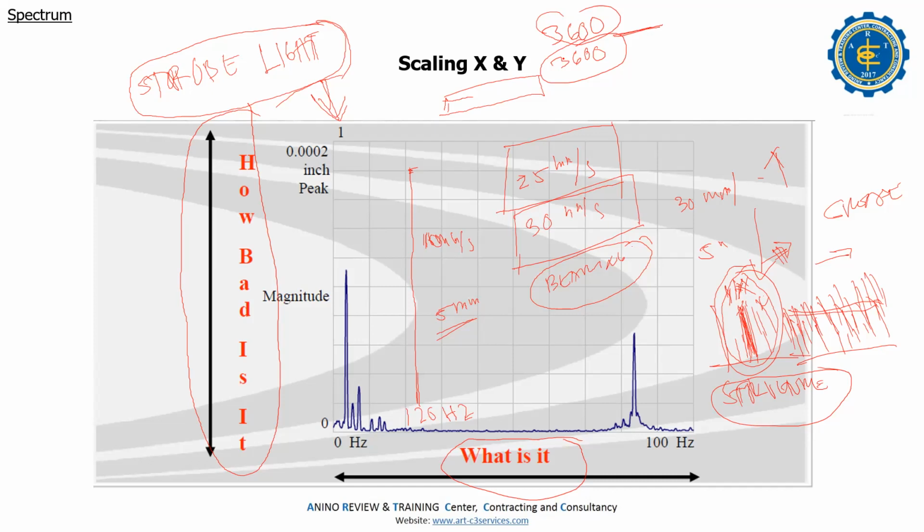Yeah, because when I do analysis, sometimes the 3x peak will come bigger. So I used to think 3x is maybe because of the coupling issues. Yeah. No, okay, I have experience with that coupling. Vertical pump. We have some vertical pumps. Okay. Yeah, vertical pumps.